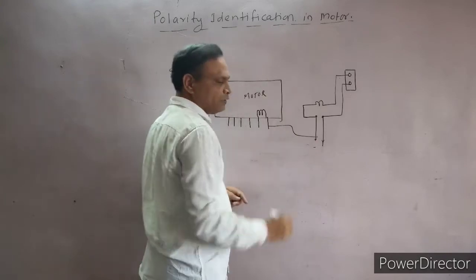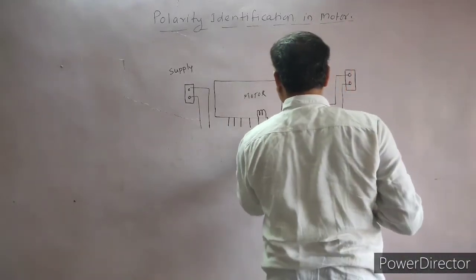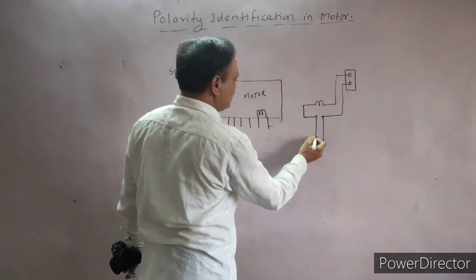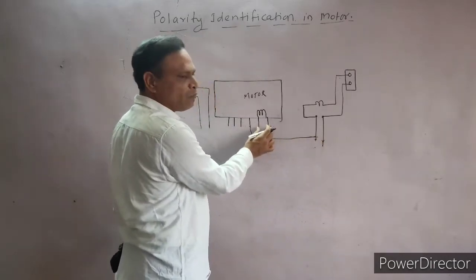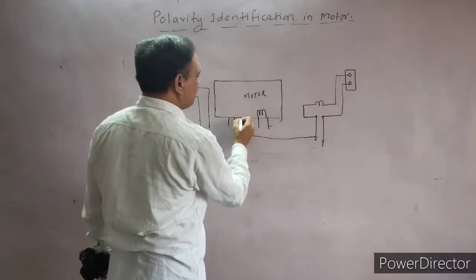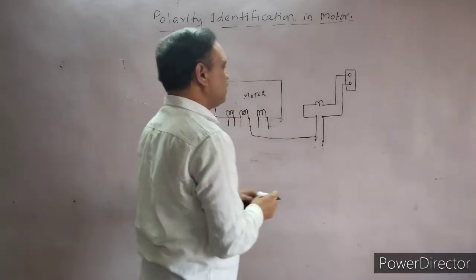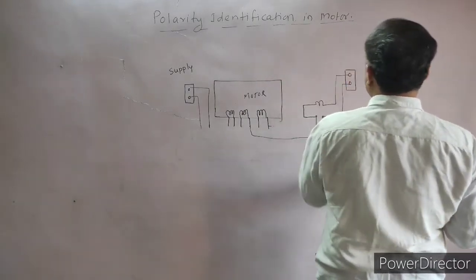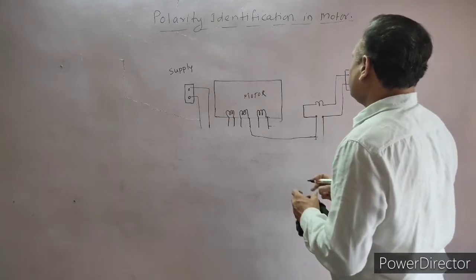Where the lamp glows, that terminal indicates a coil between the fixed terminal and the movable terminal. Let us say the coil has been found at this terminal — so there is a coil between these two terminals. Similarly, we do the same for all remaining terminals. We keep one fixed, move the probe through the remaining wires, and where the lamp glows, that's the other end of the next coil.